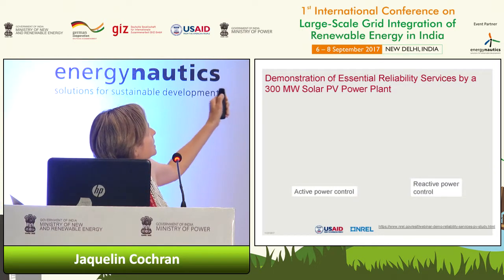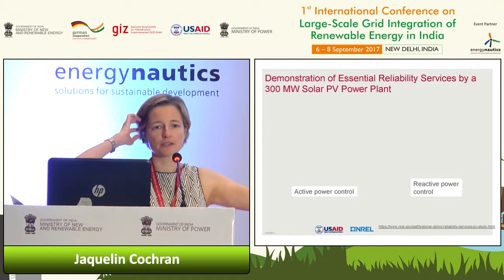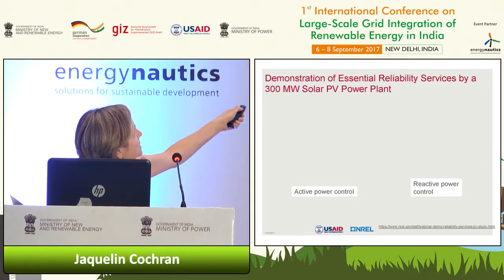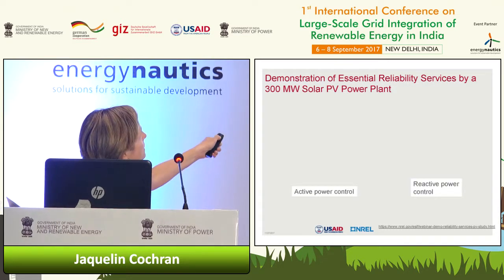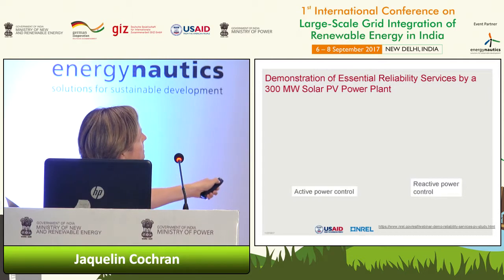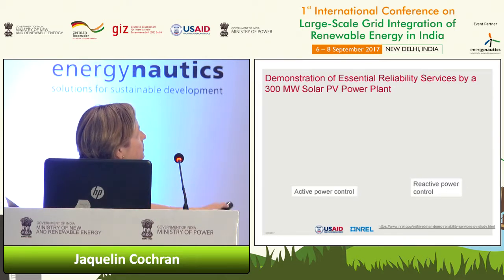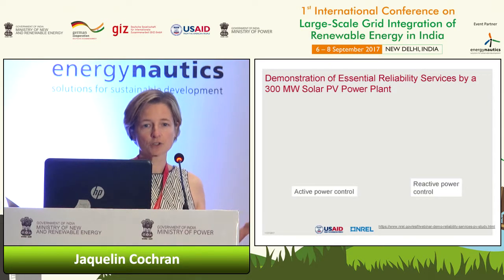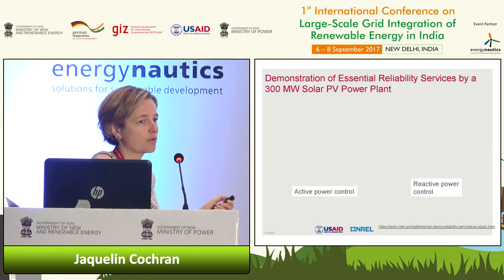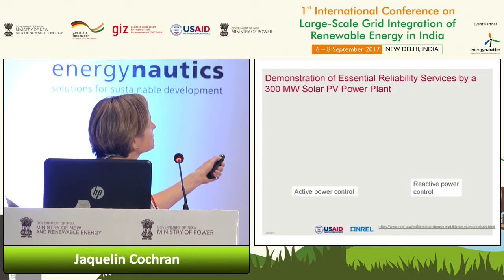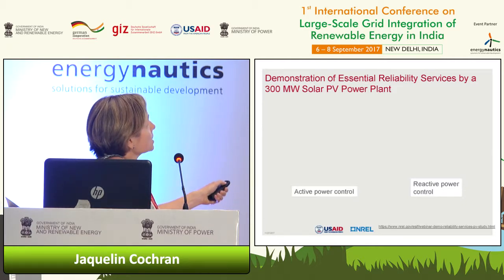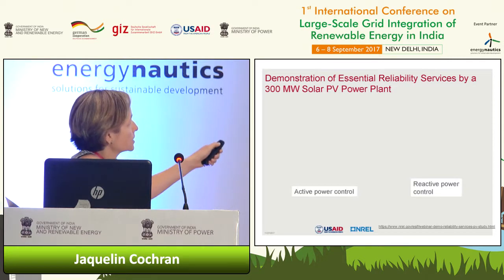Okay, there's a lot going on here, but this is part of the results of the testing that they did on this power plant. Let's start at the top here. This yellow line is the voltage. This is the active power output of the plant. This is the reactive power. This is the power in megawatts on the left, voltage on the right, and time on the x-axis. So they're testing different types of frequency and voltage support that this 300 megawatt power plant can provide. Here we see active power. With the system operator controls, they're able to bring the power down to 0, back up again. They are able to really finely control the power output based on what they're testing for.